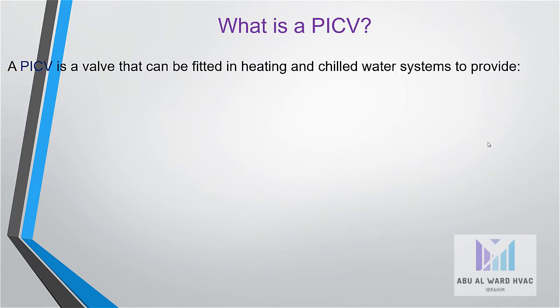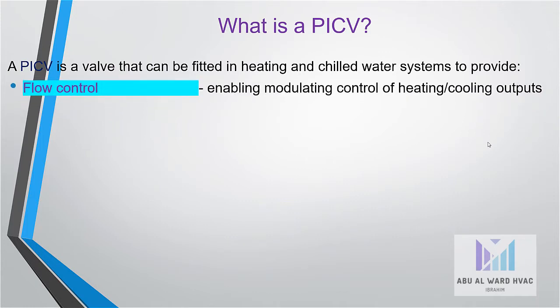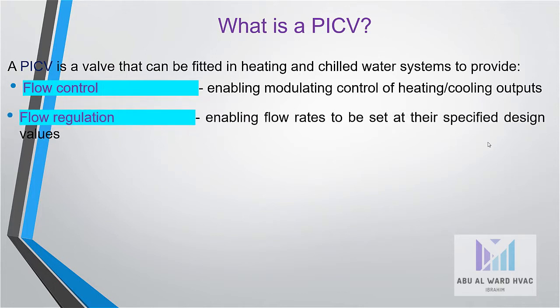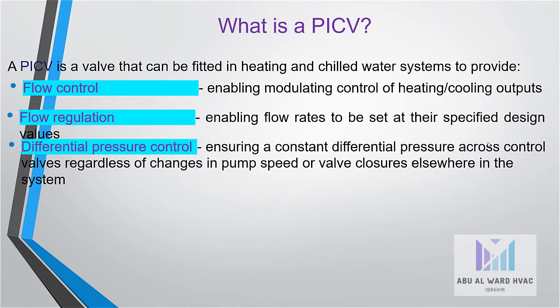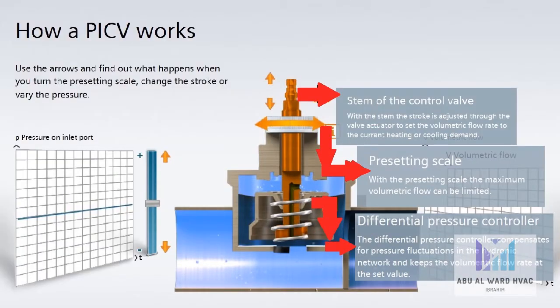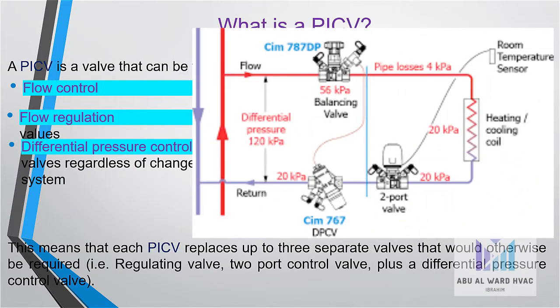What is a PICV? A PICV is a valve that can be fitted in heating and chilled water systems to provide flow control, enabling modulating control of heating and cooling outputs. Flow regulation, enabling flow rates to be set at their specified design values. Differential pressure control, ensuring a constant differential pressure across control valves regardless of changes in pump speed or valve closures elsewhere in the system. This means that each PICV replaces up to 3 separate valves that would otherwise be required: a regulating valve, a 2-port control valve, plus a differential pressure control valve.